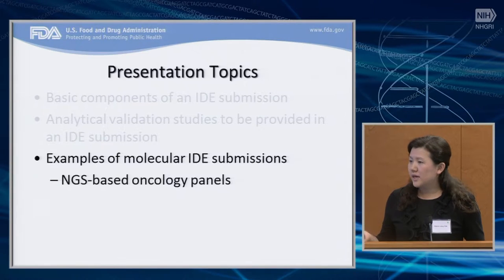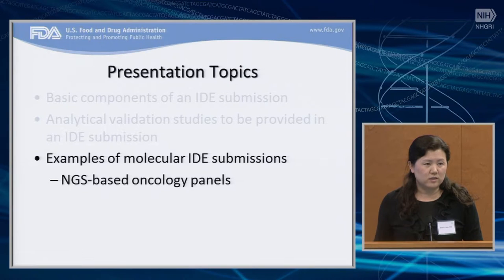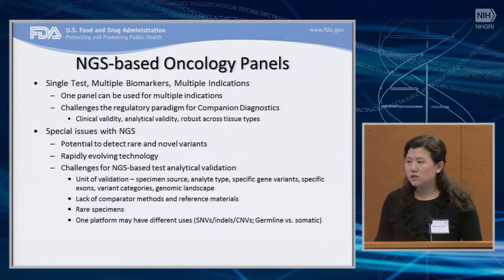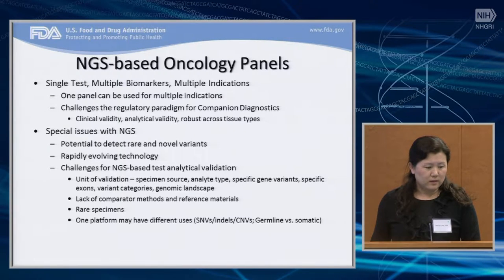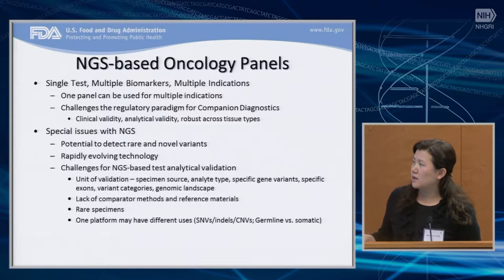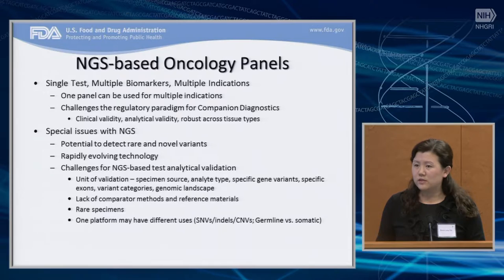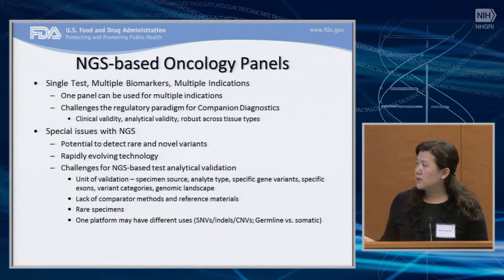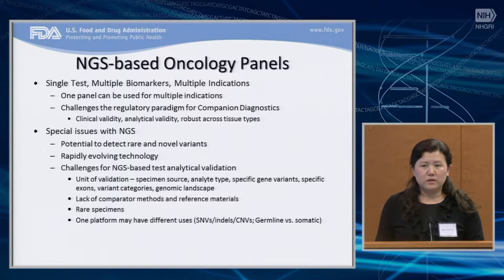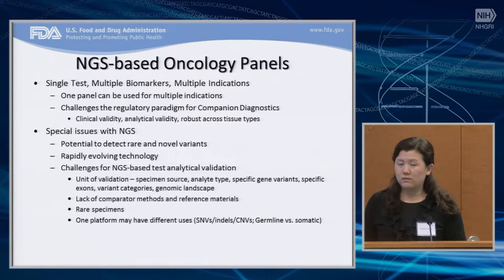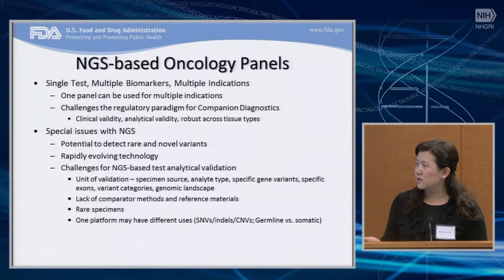I'm going to use an NGS-based ONCO panel as an example to show what analytical studies we ask for. The NGS-based ONCO panel is a single test that can detect multiple biomarkers, and sometimes it can be used for multiple indications. This creates challenges for the traditional regulatory paradigm in terms of clinical validity, analytical validity, and robustness across different tissue types. For the next-generation sequencing technology itself, it has unique challenges, such as the potential to detect novel and rare variants. The technology is evolving rapidly — there will be new aligners, new algorithms, and new chemistry coming out.